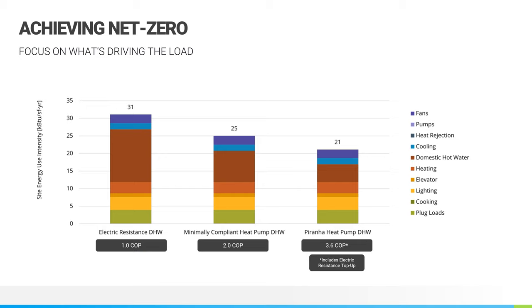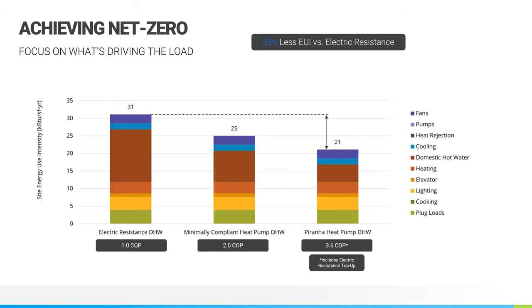So when they were doing this, they ran an energy analysis versus the three different options they could do for creating domestic hot water electrically. Versus electric resistance, there's about a 32% reduction in the site energy use intensity, which is basically the energy use divided by the square foot over the entire year. So that building became significantly more energy efficient over that time period by not going with the electric resistance. And then even the next most efficient option, where they're running a minimally compliant air source heat pump water heater, they were still 16% more efficient by going with the wastewater heat recovery heat pump.